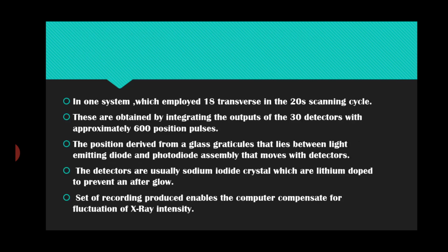The detectors are usually sodium iodide crystals, which are lithium doped to prevent afterglow. The set of recordings produced enables the computer to compensate for fluctuation of X-ray intensity.